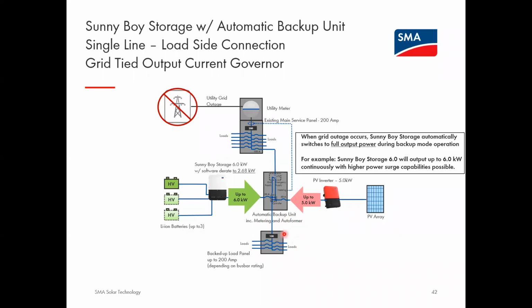In doing so, you just have to make sure that you're sizing your conductors and everything below the automatic backup unit, that's basically between the automatic backup unit and the backed up load panel, correctly according to the 120% rule. But that power never interacts in a backup event up here with the main service panel. So this is a great feature we think will increase the number of homes you can go back and retrofit with energy storage, even if you've already basically maxed out the 120% rule with your PV inverters in the main service panel.